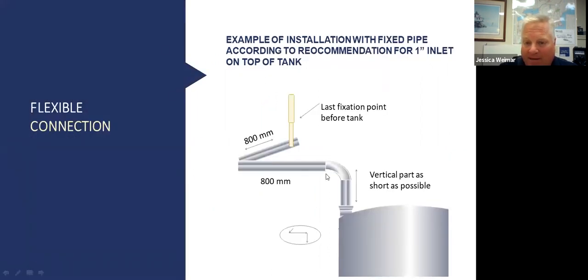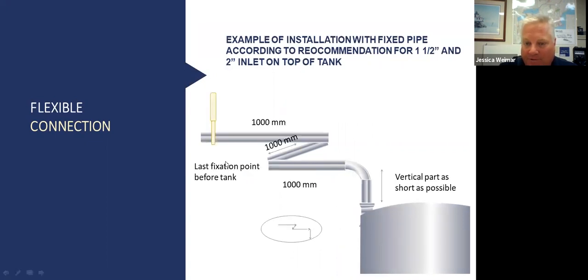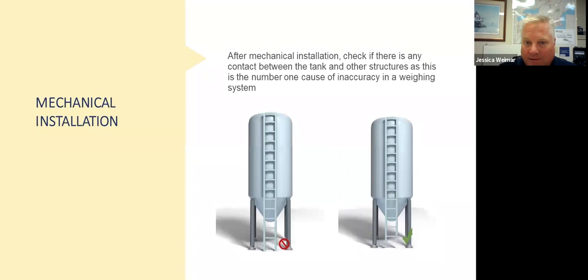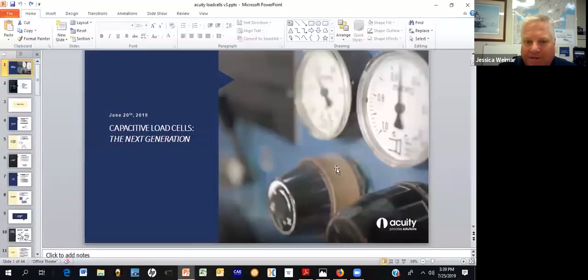If you change plane coming up to a tank, in other words, come this way, put a 90 and come back, it helps the tank to move. If you do multiple plane changes, it's an even better thing for bigger diameter pipes. Okay? So I'm not going to go too much further into the specifics of the cell for today, but what I do want people to be aware of is that the physical method that we measure is different with an Alfa Laval capacitive unit. We're not bending the sensing mechanism. We're not subjecting it to loads, to side loads, to torsional loads. We're allowing it to do what it's meant to do, which is measure. We're not making it be a structural element of the cell.